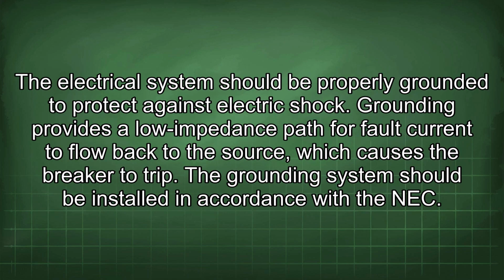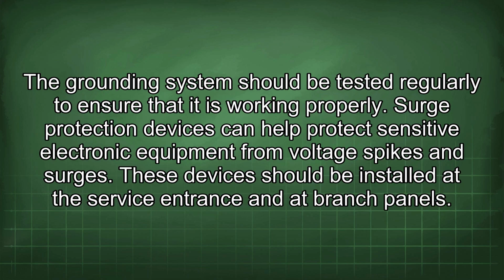The electrical system should be properly grounded to protect against electric shock. Grounding provides a low impedance path for fault current to flow back to the source, which causes the breaker to trip. The grounding system should be installed in accordance with the NEC. The grounding system should be tested regularly to ensure that it is working properly.